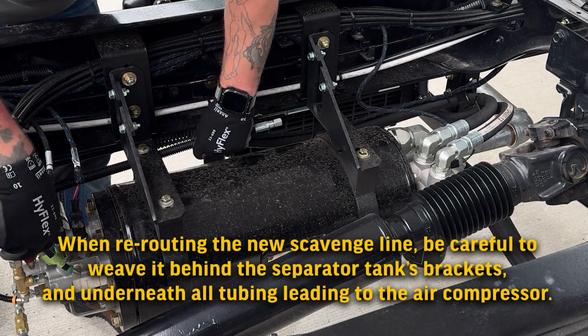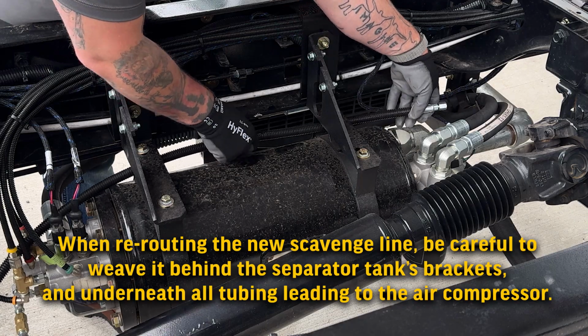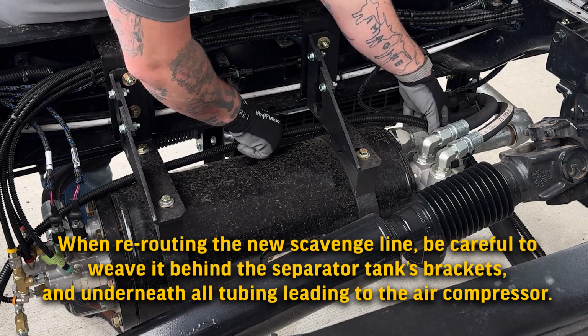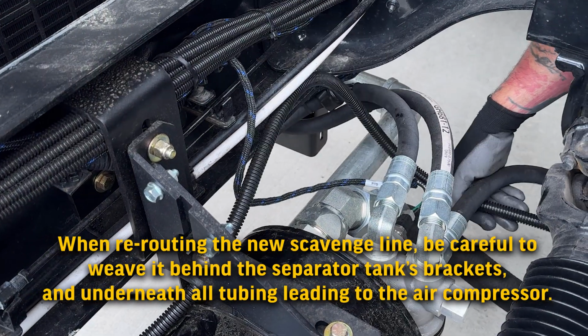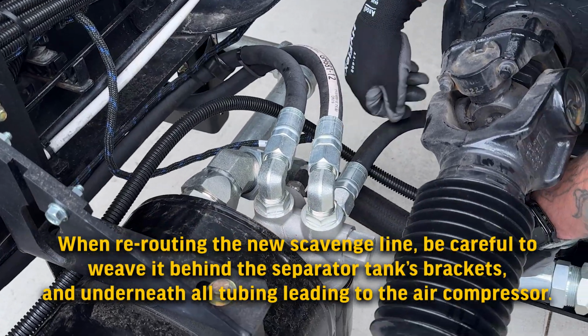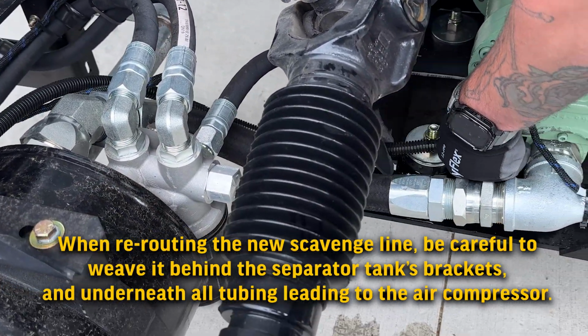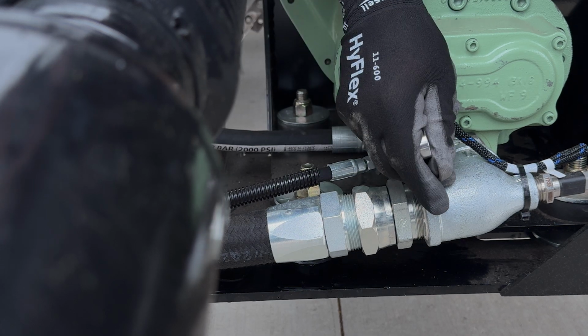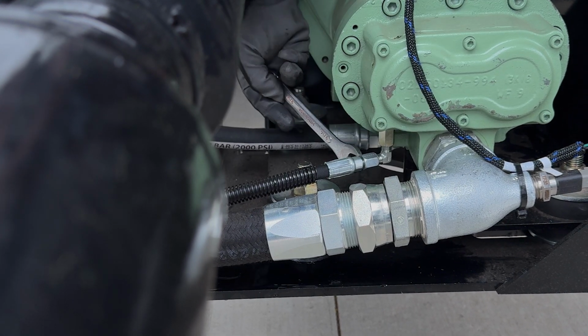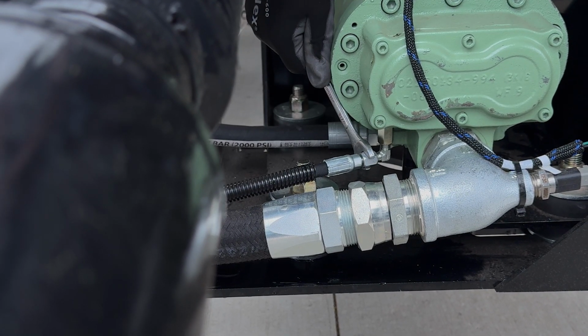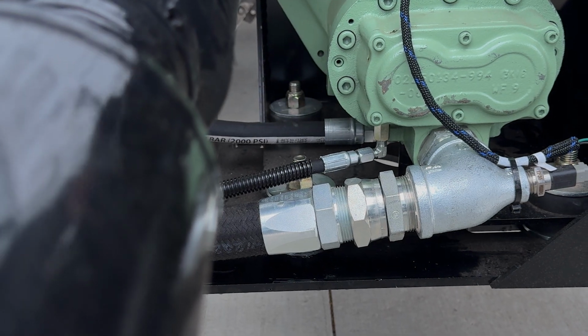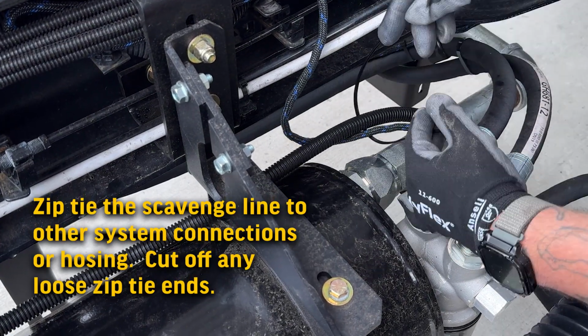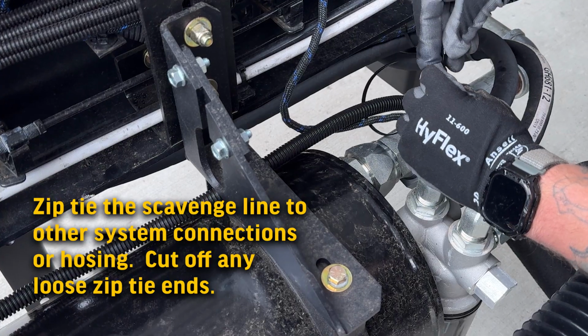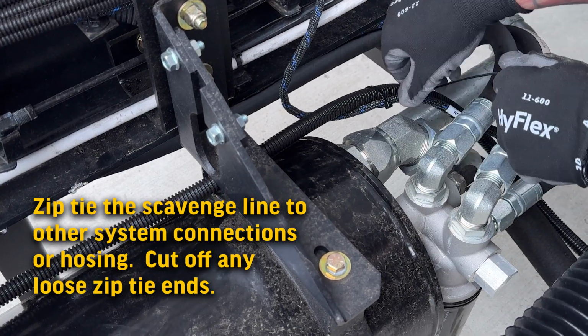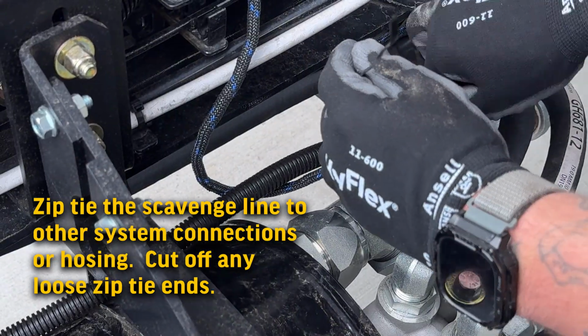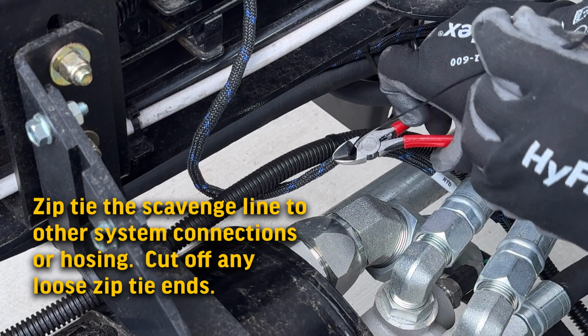When rerouting the new scavenge line, take care in weaving it behind the separator tank's brackets and underneath all tubing leading to the air compressor. Tighten the scavenge line to the air end using a 9/16 wrench. Zip tie the scavenge line to other system connections or hosing. Cut off any loose zip tie ends.